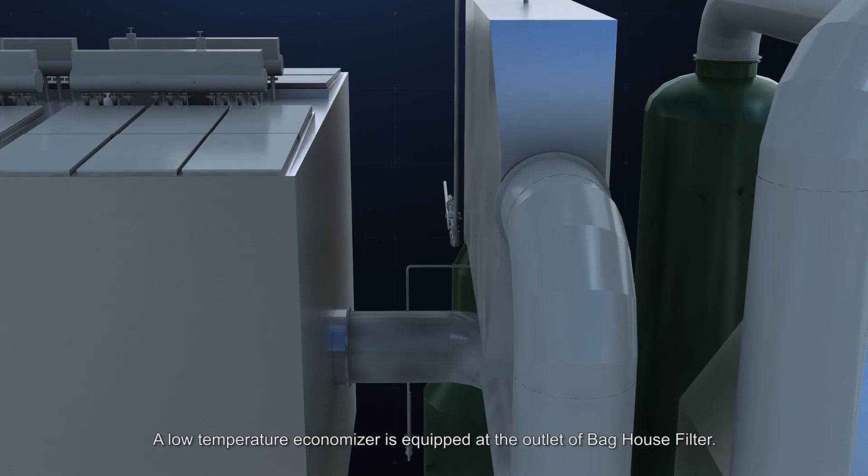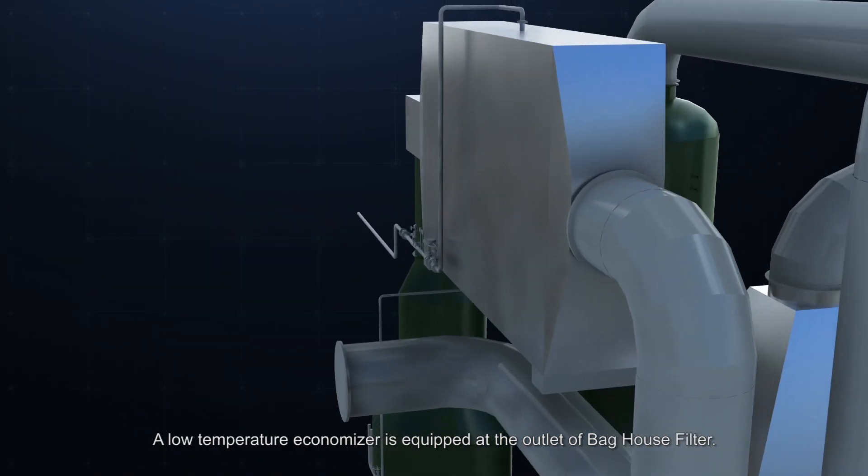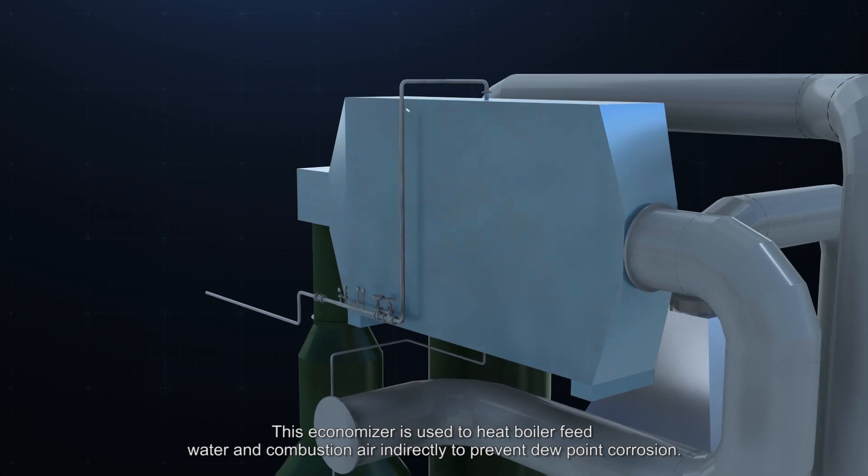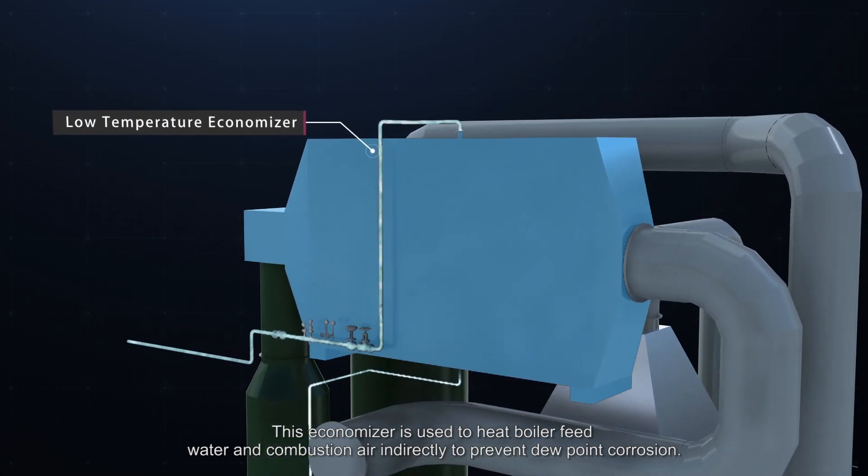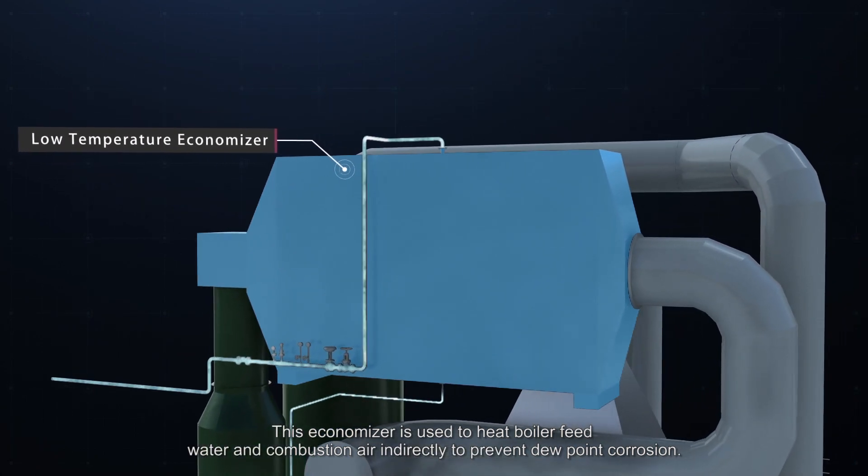A low-temperature economizer is equipped at the outlet of bag-house filter. This economizer is used to heat boiler feed water and combustion air indirectly to prevent dew point corrosion.